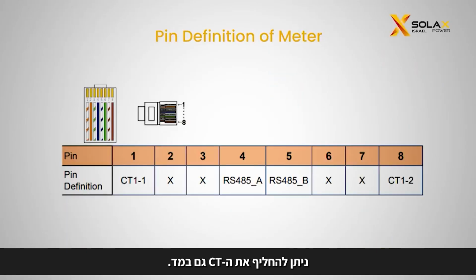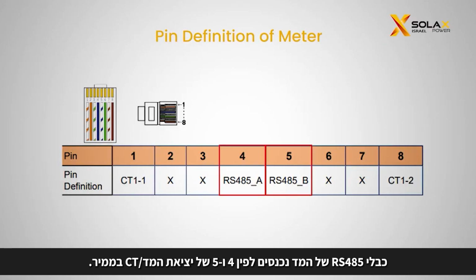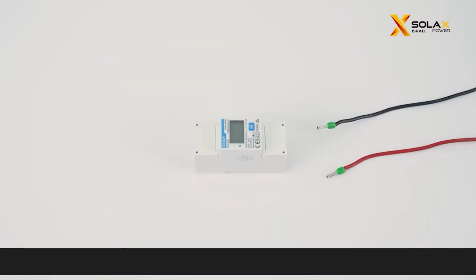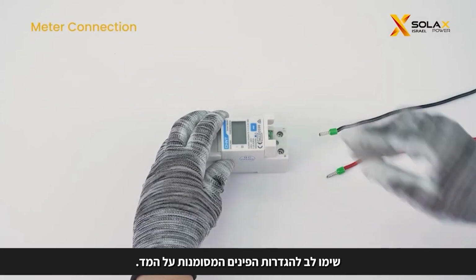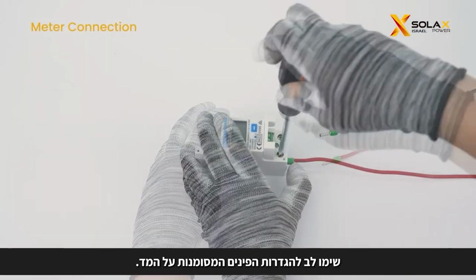The CT can also be replaced by a meter. Now we will introduce the connection of the meter. Meter RS-485 cables go to pin 4 and 5 of the meter/CT port on the inverter. Pay attention to the port definition marked on the meter.